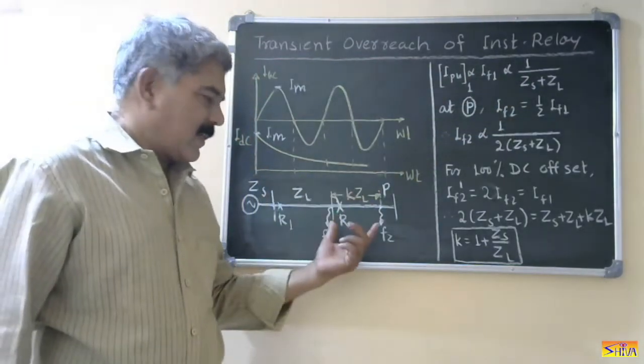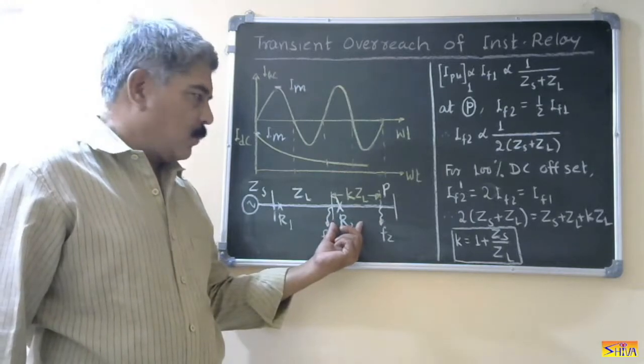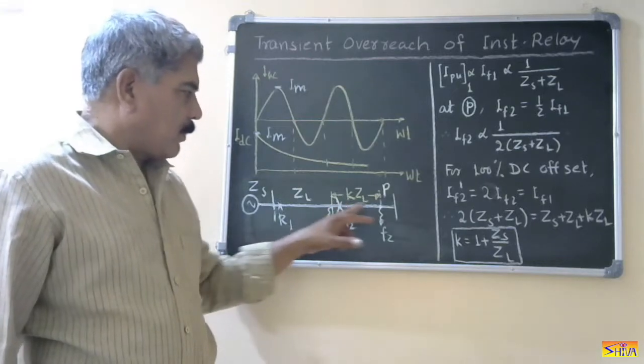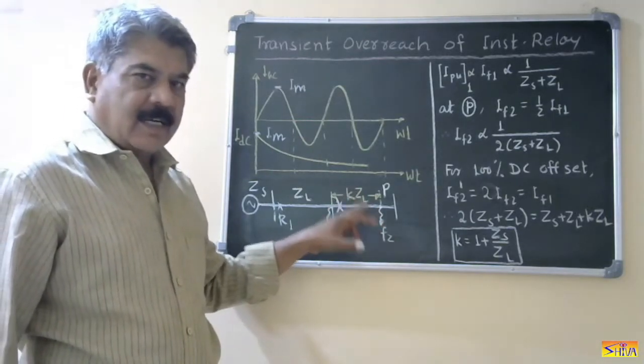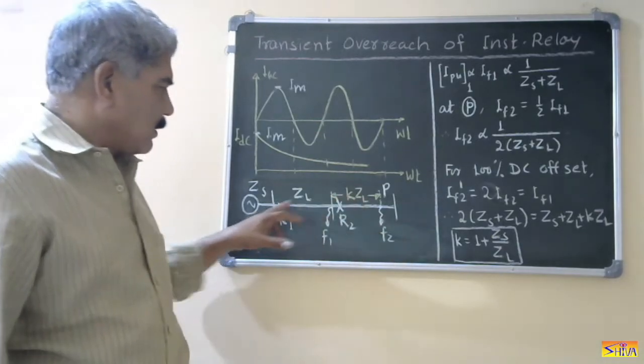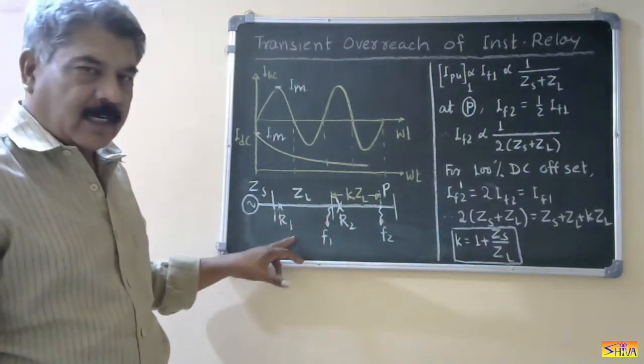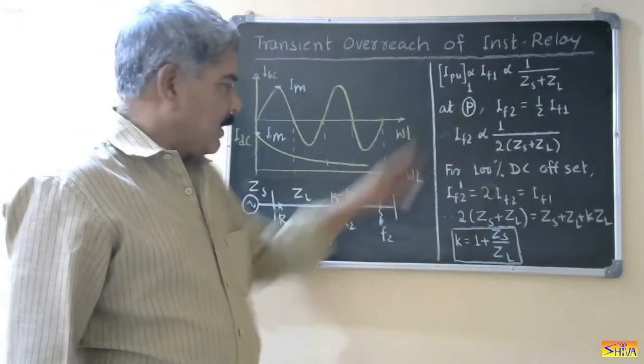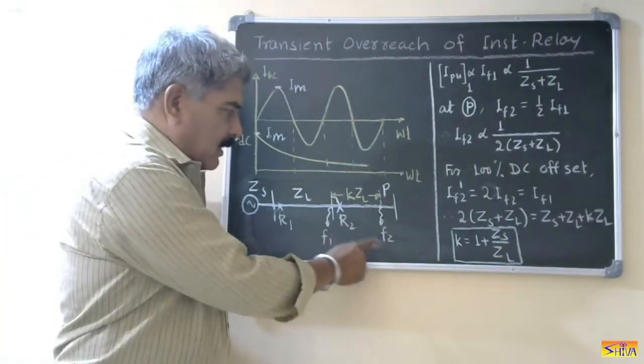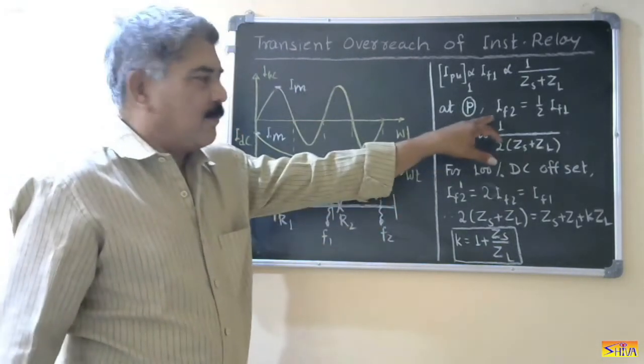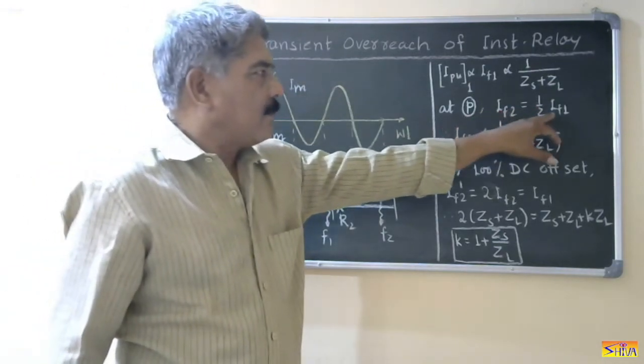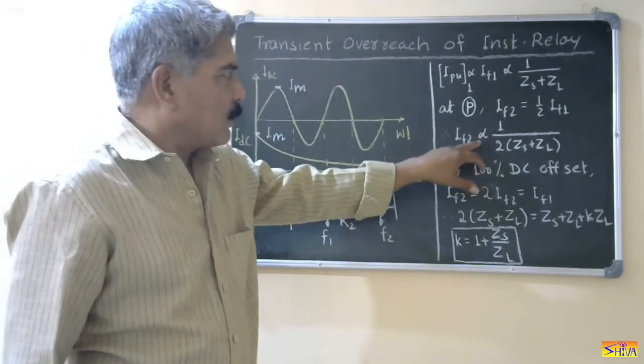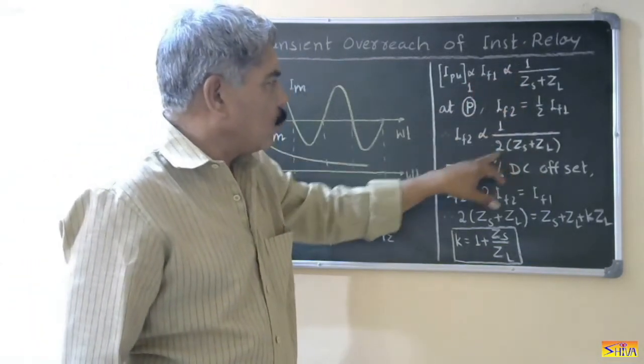In the next section covered by relay R2, consider a point P where the impedance from the relay to that point is K times ZL. ZL is the impedance of the first line protected by relay R1. At point P, if fault F2 takes place, then fault current IF2 is exactly half of fault current IF1. So IF2 is proportional to 1 upon 2 times ZS plus ZL.